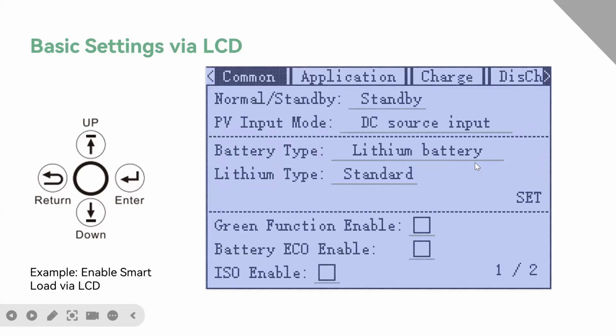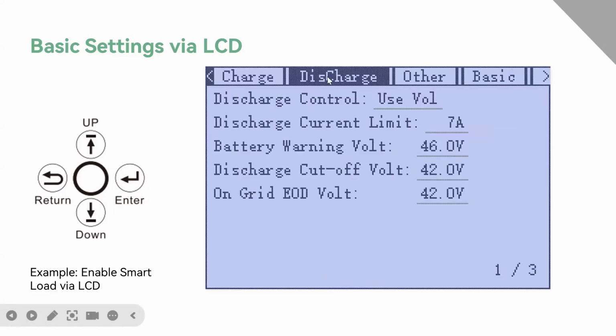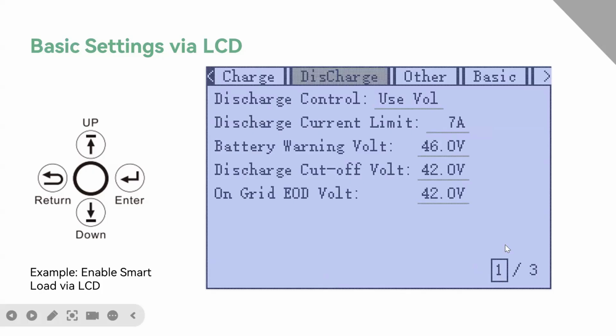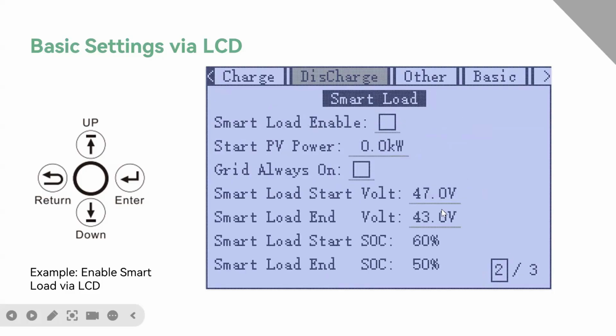Click enter again, and we can see there are different settings here, and we need to find the smart load. If we read the user menu, we will see that the smart load function is in the discharge functions. So we use the up and down buttons to go to discharge, hit enter again, and we will enter the page where we use up and down to change to the smart load page. Hit enter again, and we enter the exact setting page of the smart load function.